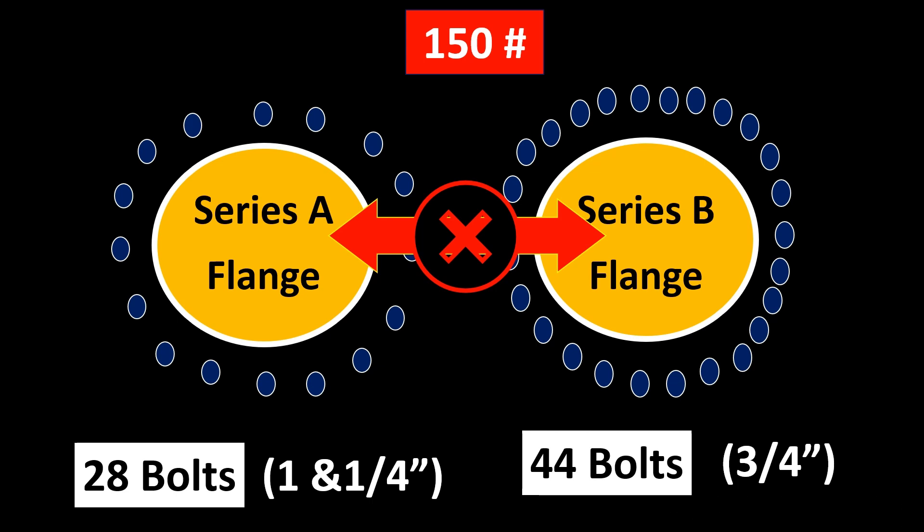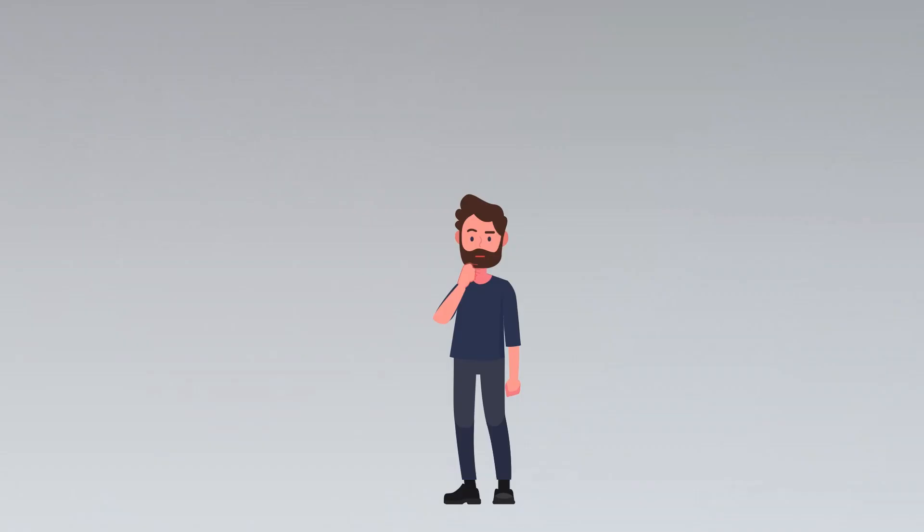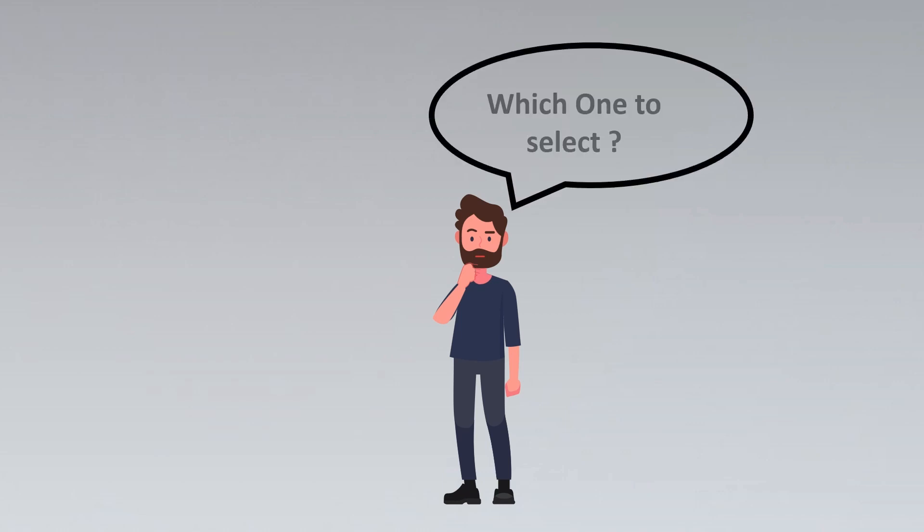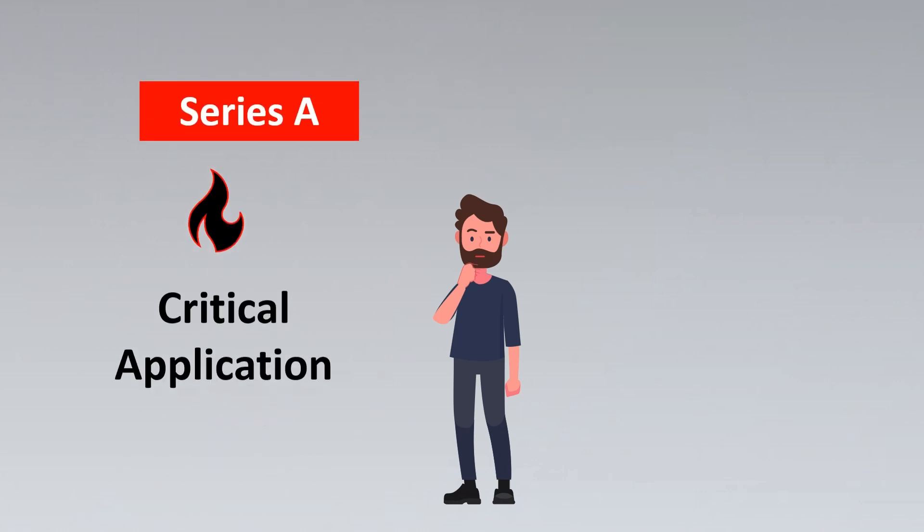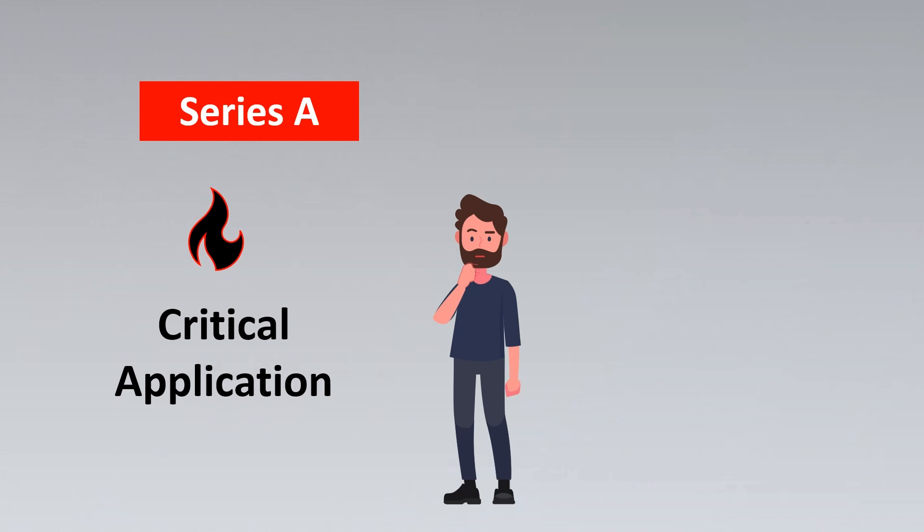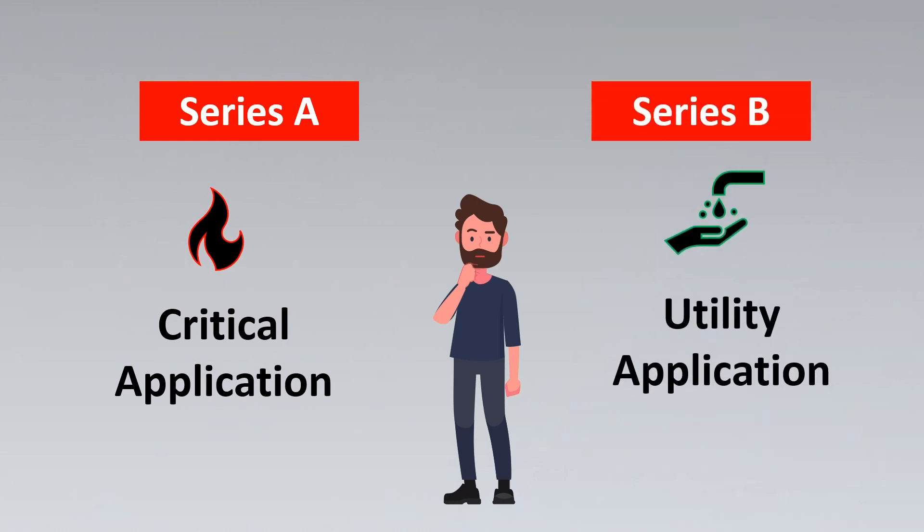Now the next question that you would have is when to select which kind of flange. We have a thumb rule for that. Series A flanges are usually used for critical applications or process applications, and Series B are usually preferred for utility applications, for example steam, water, etc., depending on the pressure and temperature ratings.